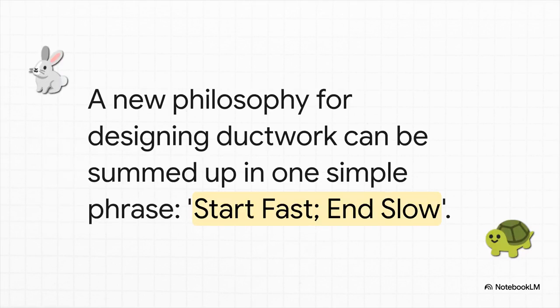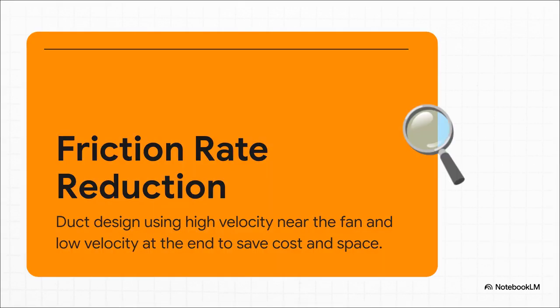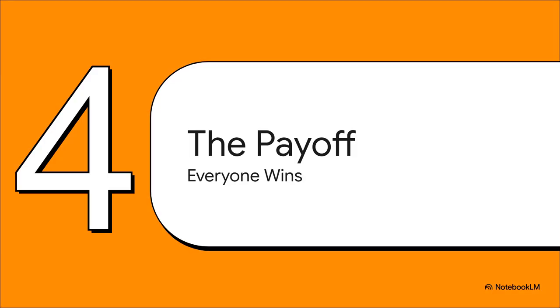This new intelligence even extends to the ductwork, all that sheet metal above the ceiling. The old ways of sizing ducts were really complicated and often led to systems that were way too big and expensive. The new philosophy can be summed up with a simple, memorable mantra: start fast, end slow. The official engineering term is the friction rate reduction method, but what it really means is you use smaller ducts and higher air speeds right near the fan where there's a lot of pressure. Then, as you get further down the line, you gradually make the ducts bigger and let the air slow down. It's an elegant approach that saves a ton of money on materials up front and helps the whole system fit into tighter spaces.